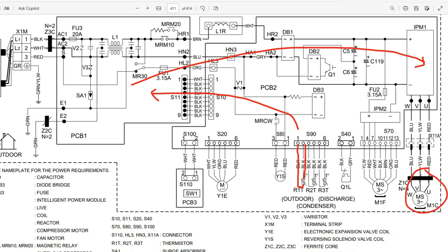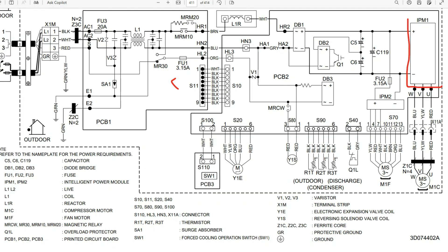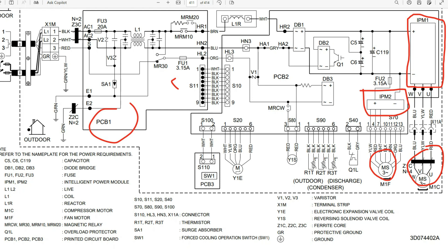At what capacity the compressor will run, the outdoor fan motor, the indoor fan motor, and so on. We have two intelligent power modules here — one dedicated solely for the compressor, and another dedicated to the outdoor fan motor. These power modules carry out the commands coming from the PCB to regulate the power supply into these motors so that we can run them at very specific capacities.